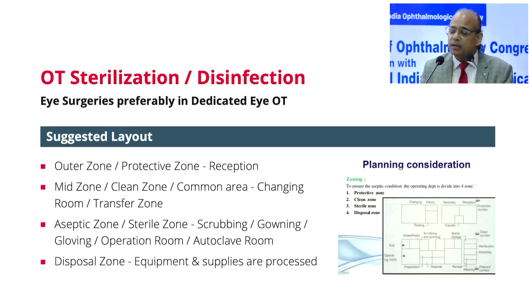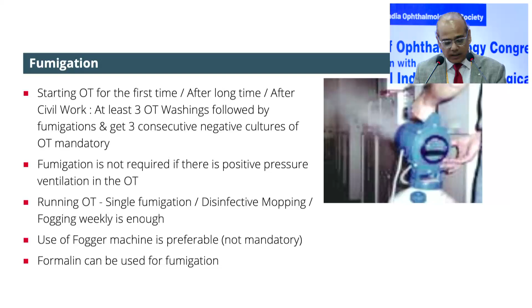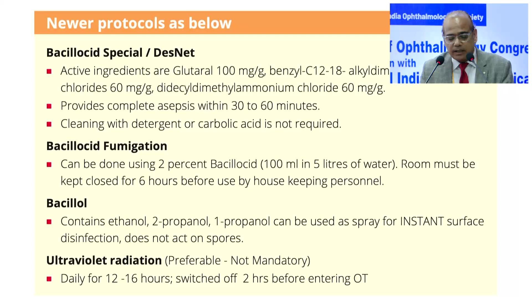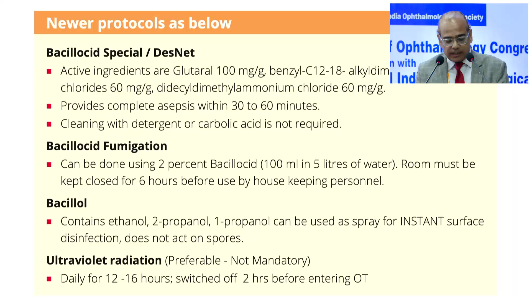Fumigation: when starting an OT for the first time after a long time or after civil work, at least 3 OT washings followed by fumigations are needed, and 3 consecutive negative cultures in the OT are mandatory. Fumigation is not required if there is positive pressure ventilation in the OT. In a running OT, a single fumigation or disinfectant mopping or fogging weekly is enough, and use of a fogger machine is preferable, not mandatory. Formalin can be used for fumigation, but now there are newer protocols, so it is no longer needed. Bacillocid Special or Desnet, whose active ingredient is glutaraldehyde 100 milligram per gram, and Bacillocid fumigation, and ultraviolet radiation are preferable; ultraviolet radiation is not mandatory.